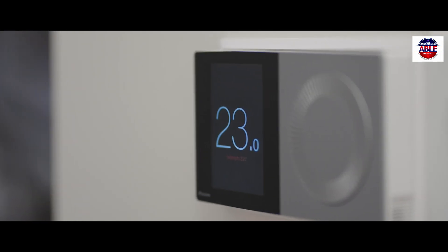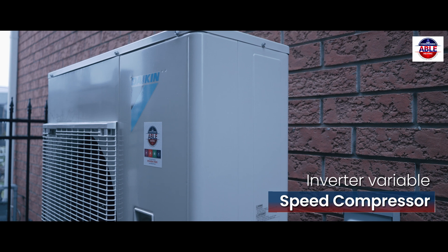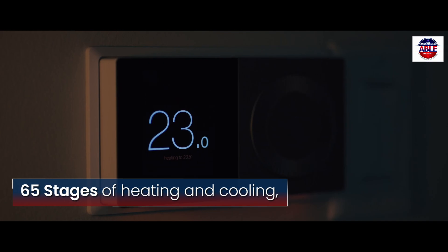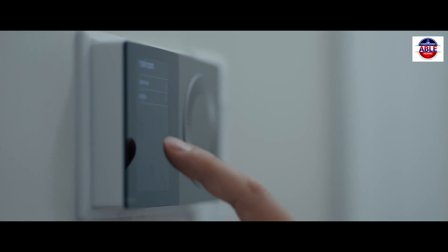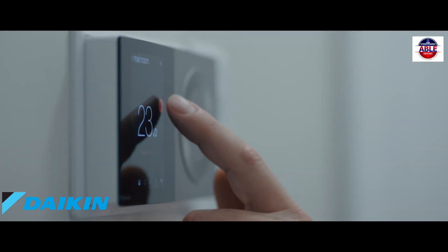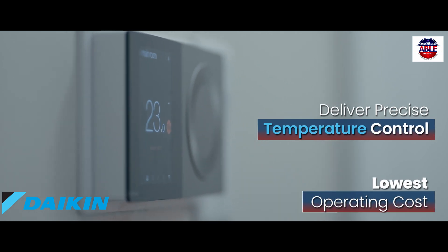One: a full two-way communicating thermostat. Why? Almost all cold climate heat pumps come with an inverter variable speed compressor. The compressor has over 65 stages of heating and cooling — a modulating system — which is great because it can deliver precise temperature control at the lowest operating cost.